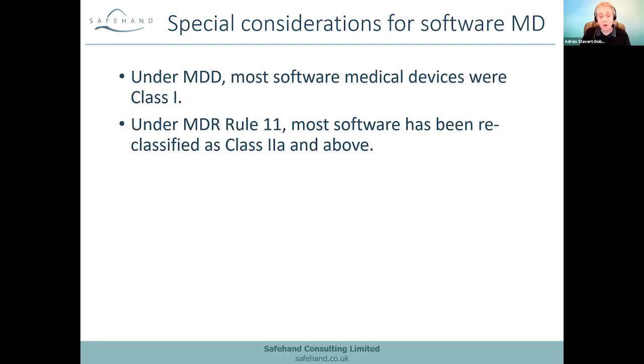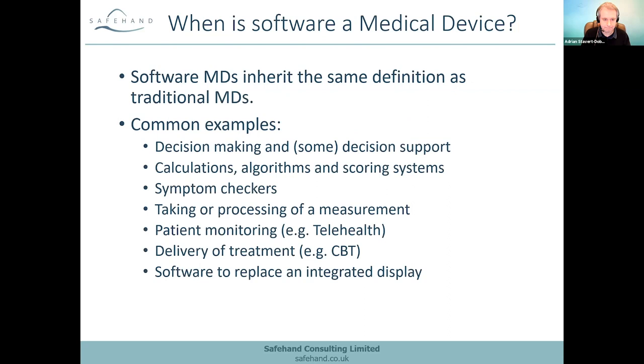Unfortunately, come MDR, all of that changes. With the introduction of Rule 11, the vast majority of software will now be reclassified as at least a Class 2A or above medical device. That has radical implications, particularly for traditional software manufacturers, where it's a step change in what they're obliged to do. I'll say a little more about that shortly.